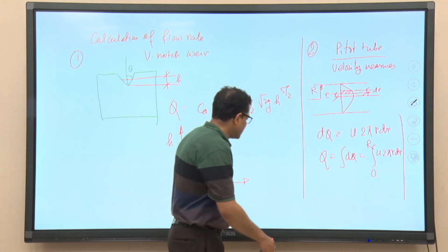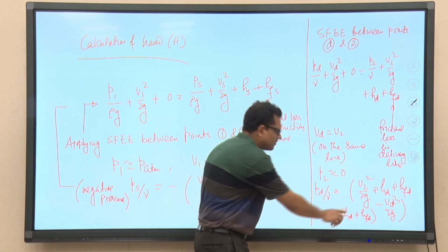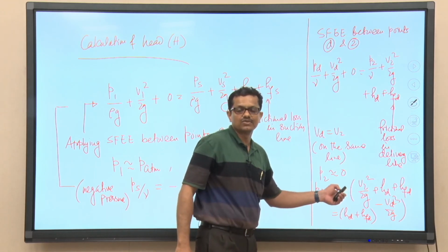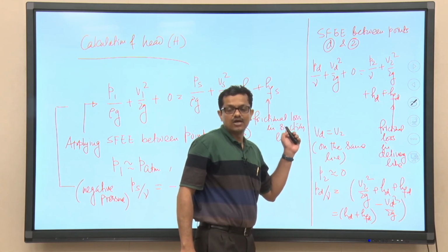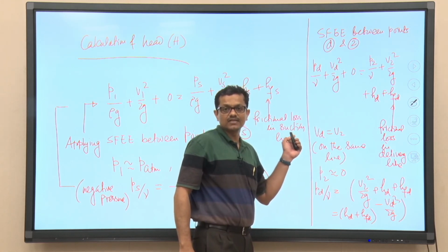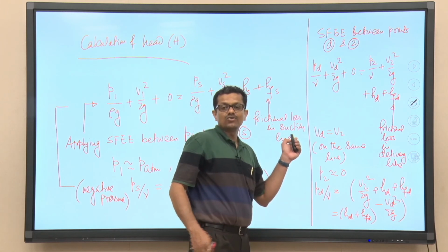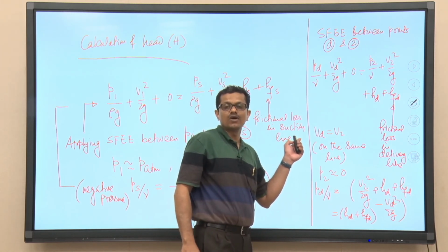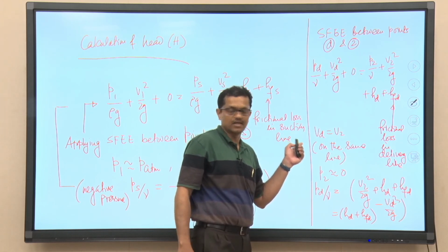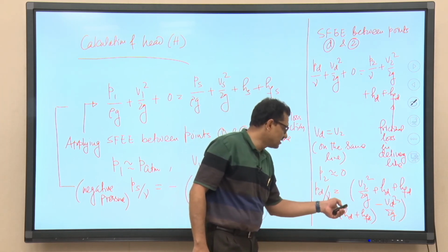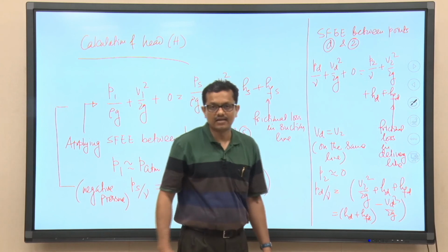So, from this equation we can see this is nothing but the head that is being developed by the pump. That is the static pressure reading that we are getting from the delivery gauge, and as I discussed in the previous class, when we talk about reaction of a pump, there are two pressure components, static pressure as well as dynamic pressure. So, not only are you getting the static pressure, you will also be getting the delivery head, right.